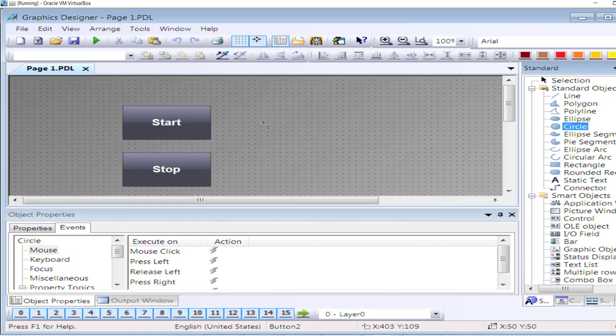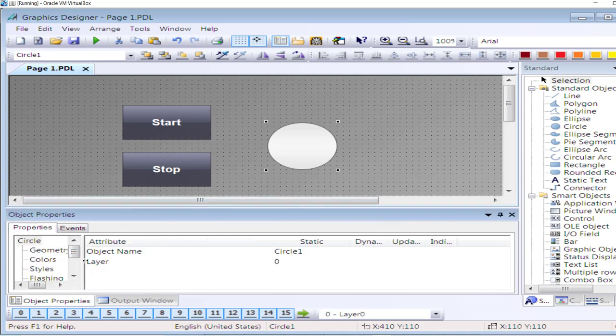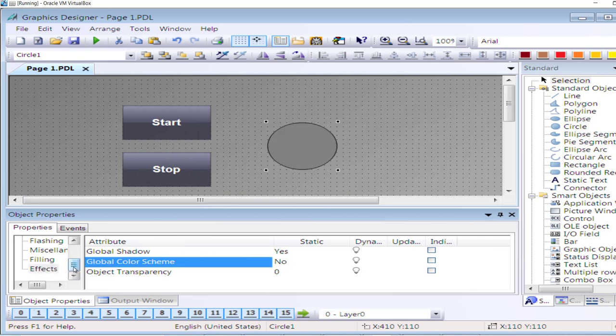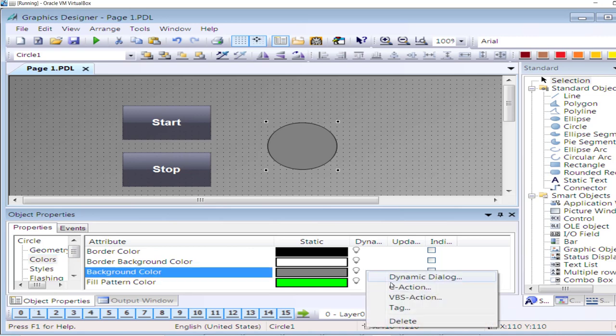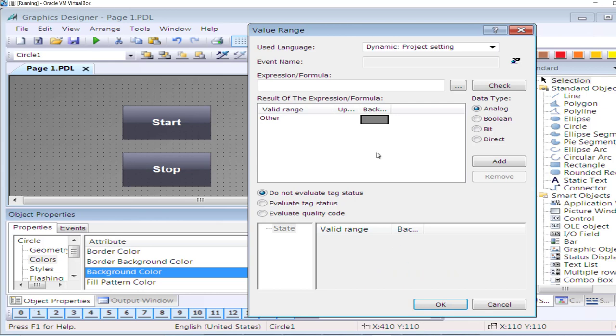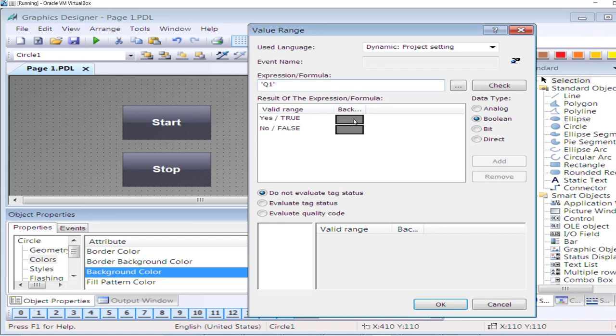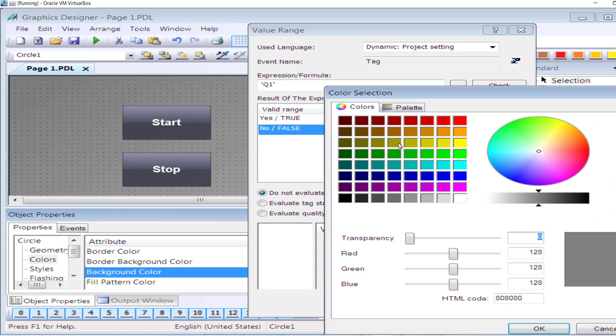For further demonstration I will display the status of the motor. I'll use a circle. Go to the properties on this circle — the global color scheme has to be off in order for this circle to show its true colors. In the background color I will associate the tag using a dynamic dialogue boolean — take Q1. Whenever Q1 is high it will be green, and whenever Q1 is low it will be red.